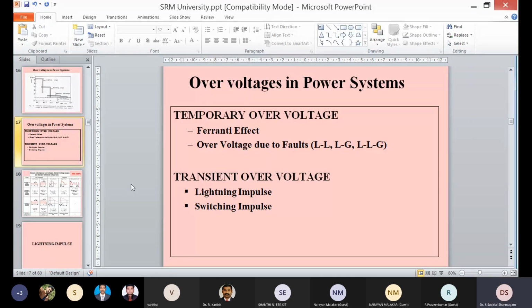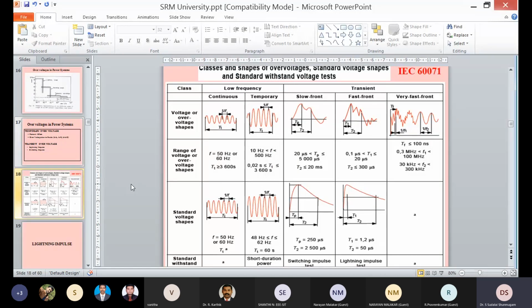And when I say temporary overvoltage or power frequency overvoltage, it comes under the Ferranti effect, line to line fault, or line to ground fault. When I say transient surges or impulse voltage, the broader classification is switching impulse as well as lightning impulse. So right now we will speak only about the high voltage line, that is system voltage less than 245 kV. I will define what power frequency withstand voltage and lightning impulse are. Then we will go to the next level. We will define switching impulse also. Then finally we will cover pollution.